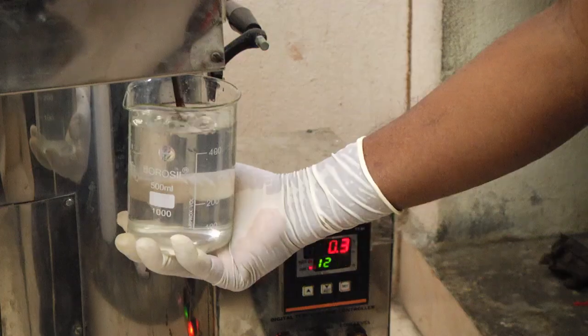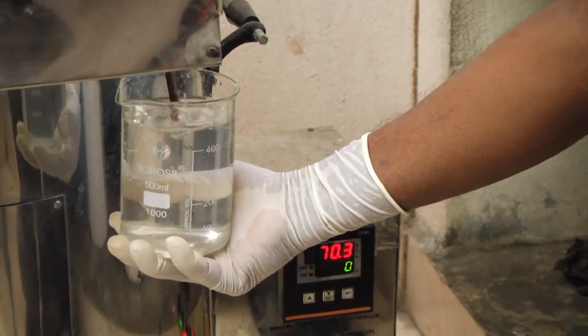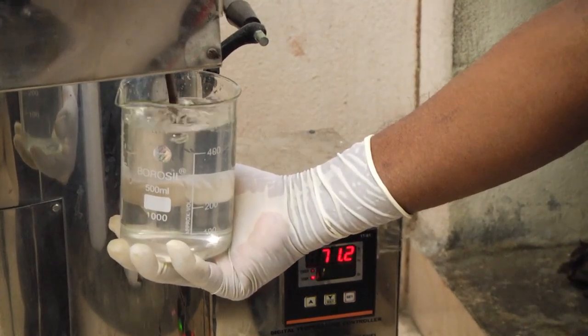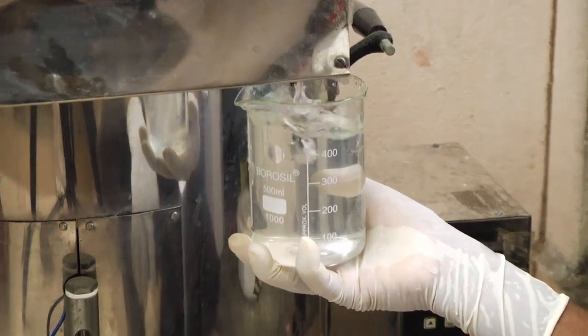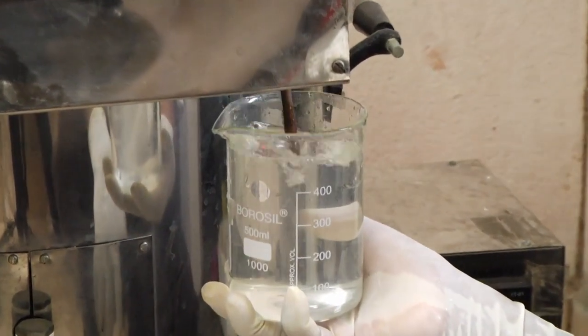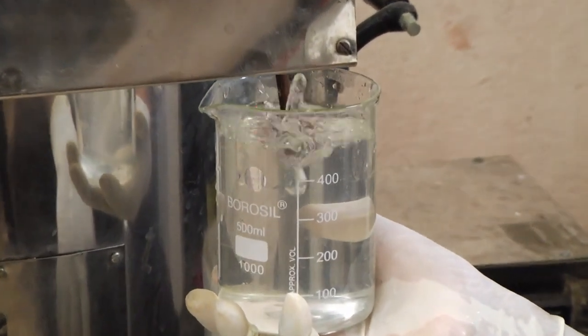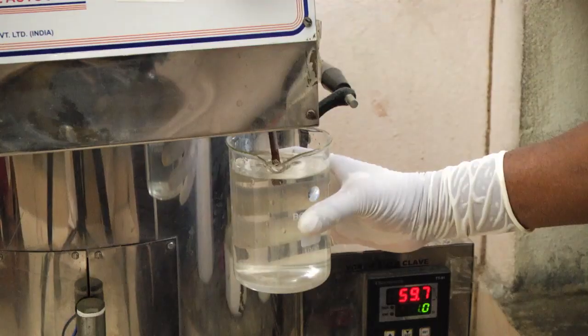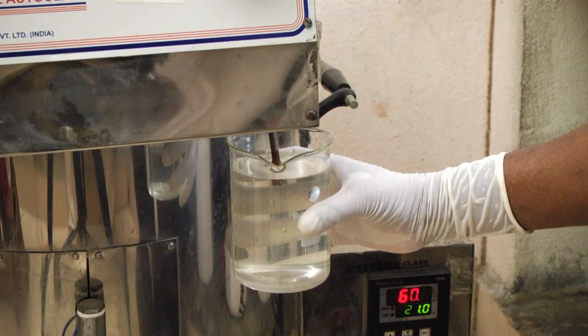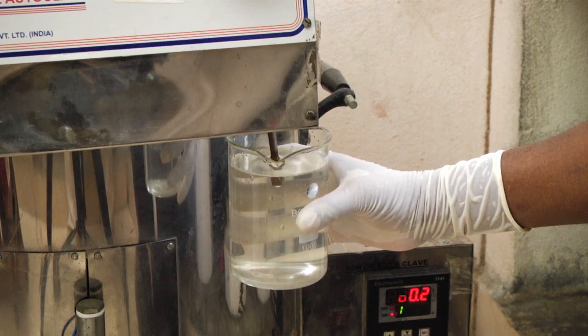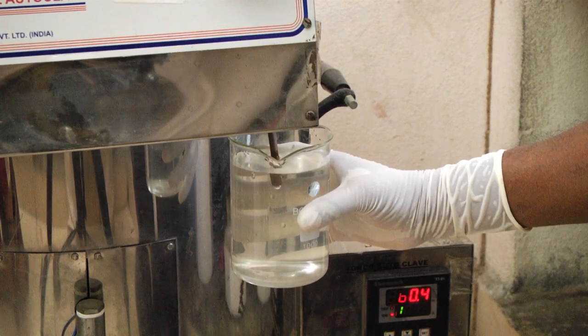It is possible to check whether all the air has been removed from an autoclave by connecting one end of a length of tubing to the air outlet and immersing the other end in a container of water. All the air has been expelled when no more bubbles can be seen emerging from the tubing into the water.